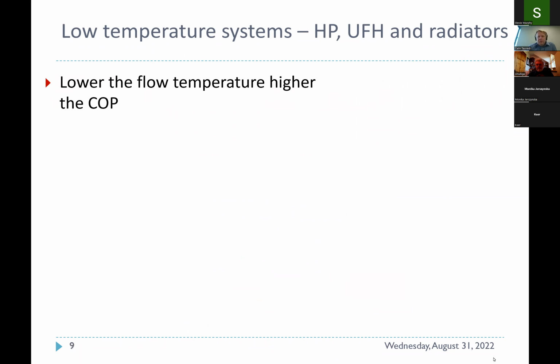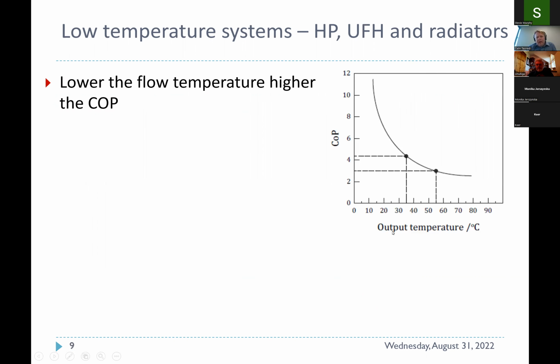I have a little graph here just to show the dependence between flow temperature and COP. Obviously, the higher the temperature, because we need more electrical power input for the thermal power output we get, the COP will be lower. So typically, for a low temperature radiator system, where we have temperatures around 40-45 degrees, you're looking at a seasonal COP around 4. And on underfloor heating systems at around 30, 35 degrees, we're looking at a COP close to 5. When we produce domestic hot water, an average seasonal COP for that will be 2.5 to 2.8.